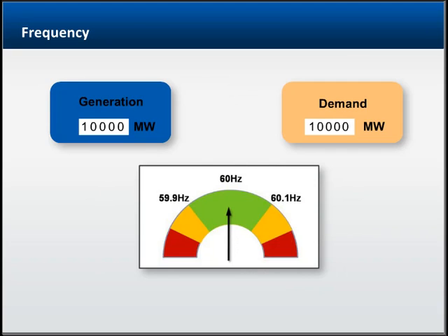Frequency is determined by the speed of rotation of the generators that provide power to the system. As demand begins to exceed the available power on the grid, the generator's speed of rotation slows slightly, resulting in falling frequency.